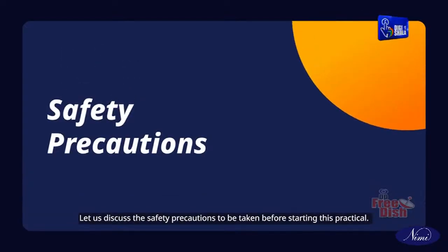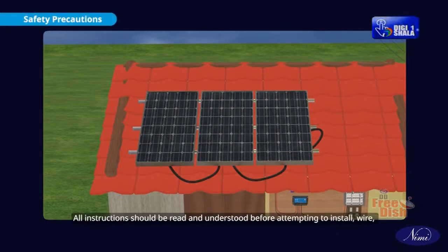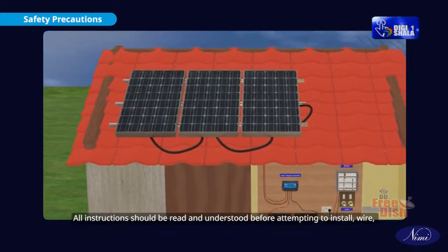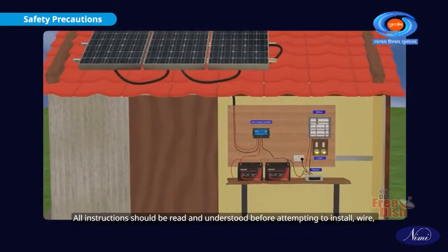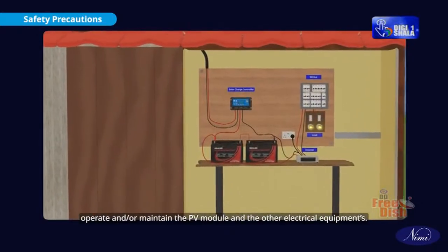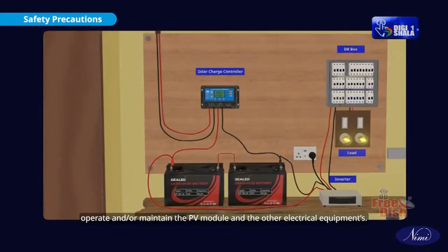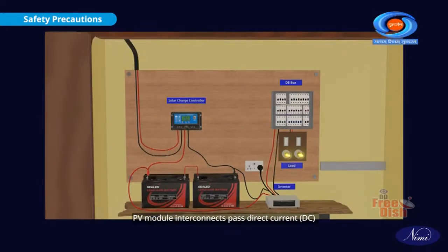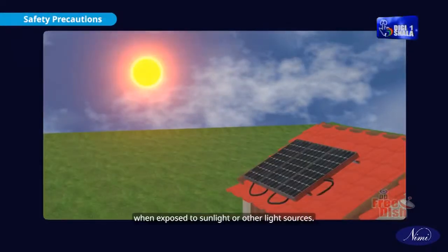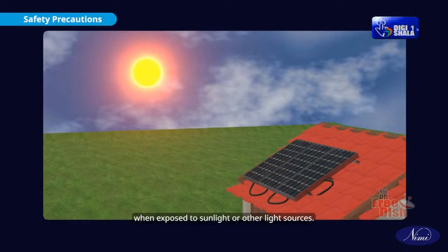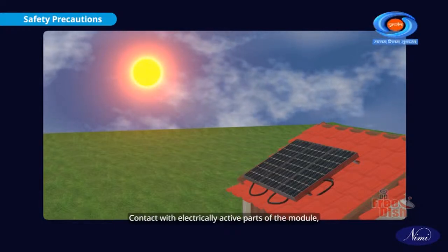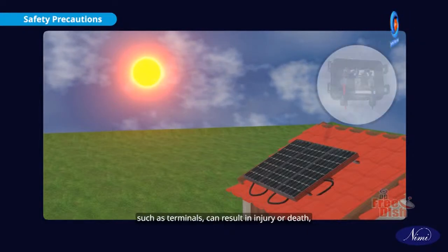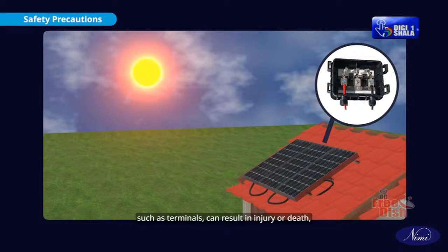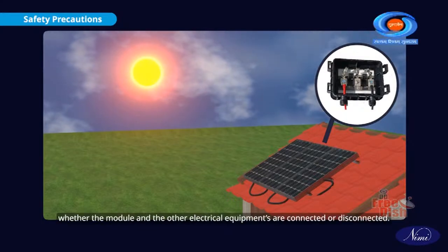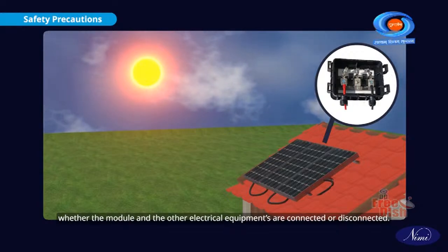Let us discuss the safety precautions to be taken before starting this practical. All instructions should be read and understood before attempting to install, wire, operate and/or maintain the PV module and the other electrical equipment. PV module interconnects pass direct current (DC) when exposed to sunlight or other light sources. Contact with electrically active parts of the module, such as terminals, can result in injury or death, whether the module and the other electrical equipment are connected or disconnected.